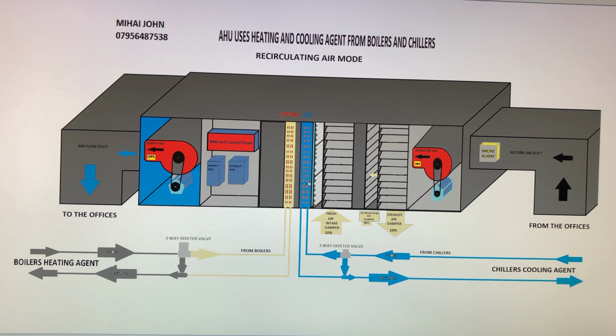If the temperature in the store drops and drops and drops, it will come to the point where the building management control will restrict the flow completely, because the temperature drops too much. And then it will bring it back if the temperature starts rising again. So you only play with a diverter valve, because the chiller works for multiple AHUs. If there is only one AHU on the roof, then yes, it could activate the chiller as well, but the chiller sometimes has its own running protocol. Most of the time I've seen chillers running on their own control, but sometimes I saw a lot of chillers running on the building management control command. So if the AHU needs it, we'll enable the chiller.